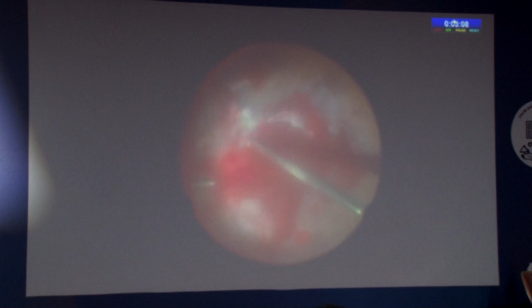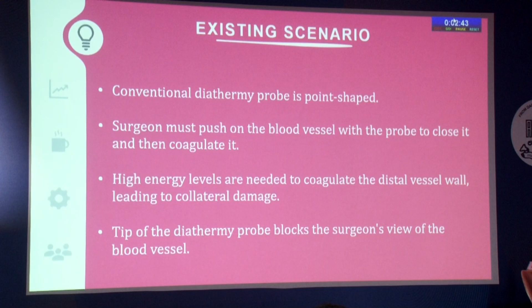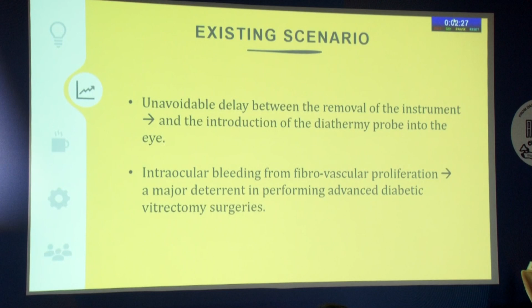So let's look at the existing scenario. Conventional diathermy probe is point shaped. The surgeon must push on the blood vessel to close it and coagulate it. High energy levels are needed, sometimes causing collateral damage. Tip of the diathermy probe is blocking the surgeon's view and hence can sometimes damage the underlying tissues as well. And there is always an unavoidable delay, like we saw in the video, when taking one instrument out and putting the other in. So this will prevent you from doing a perfect or a good advanced diabetic vitrectomy surgery.